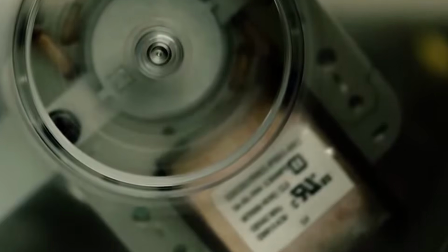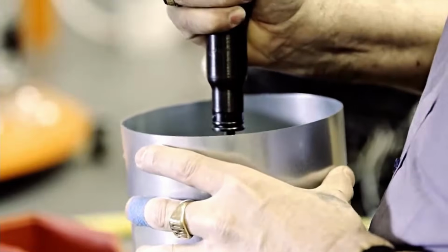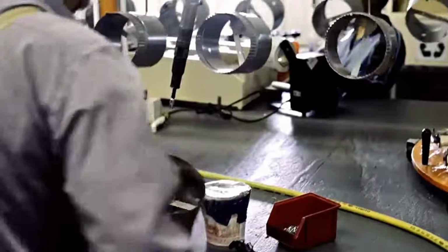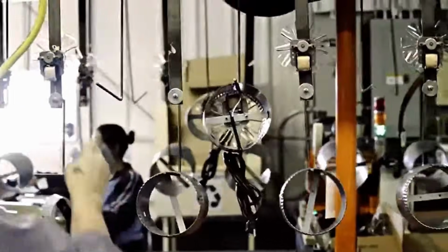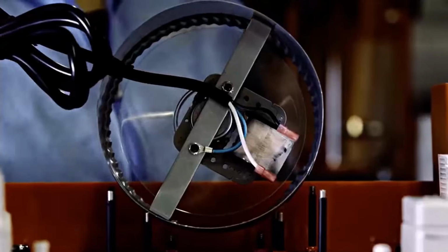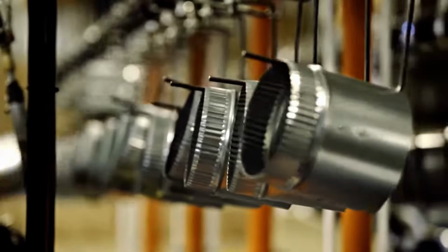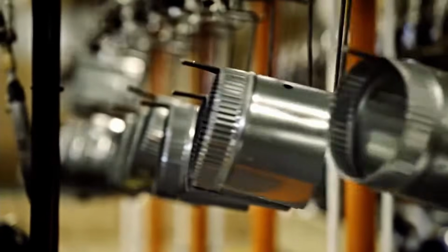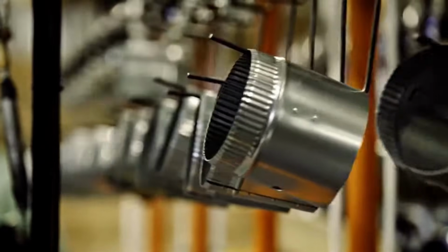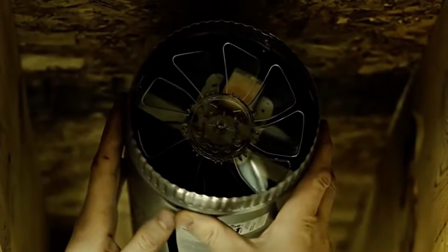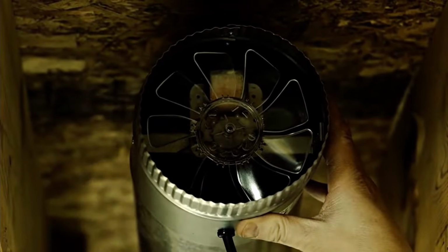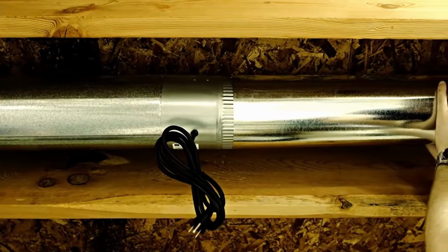Installing a booster fan. The booster fan is designed to increase the airflow to the more distant parts of a home. On the market currently there are 2 types of booster fan: inline duct booster fans and register booster fans. Inline duct booster fans are built to be installed inside the ductwork itself. Because they can shift large volumes of conditioned air, inline fans are often used in larger properties with extensive networks of air ducts.